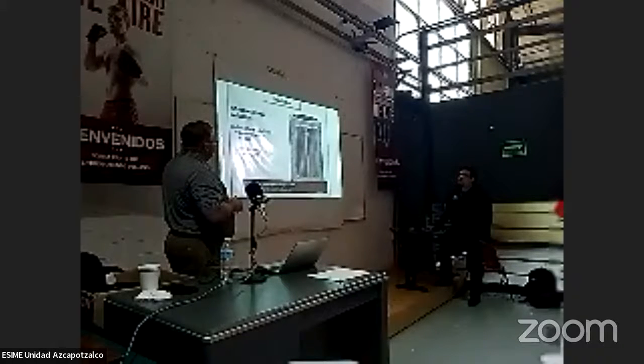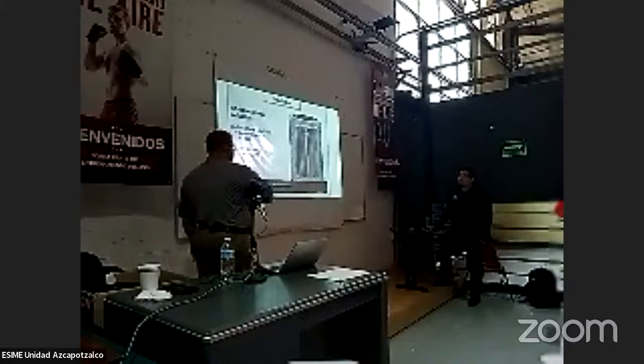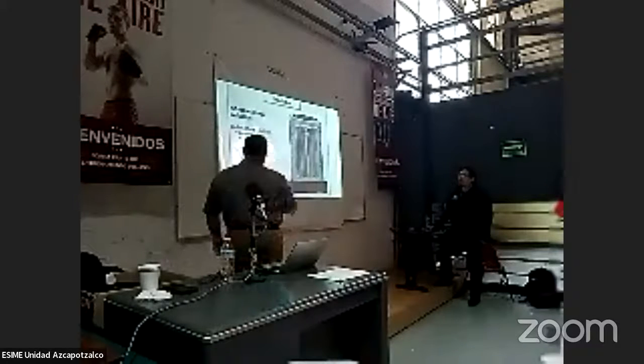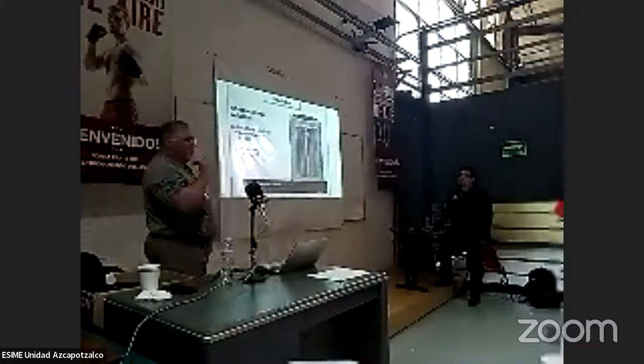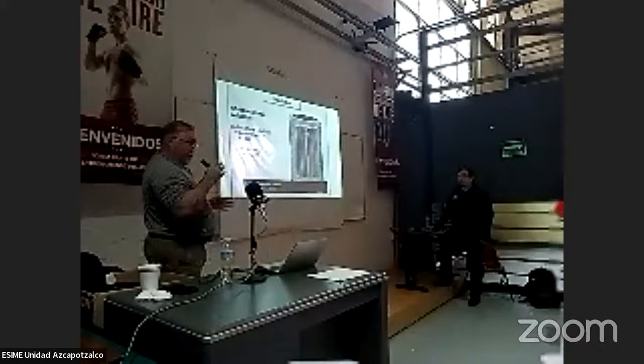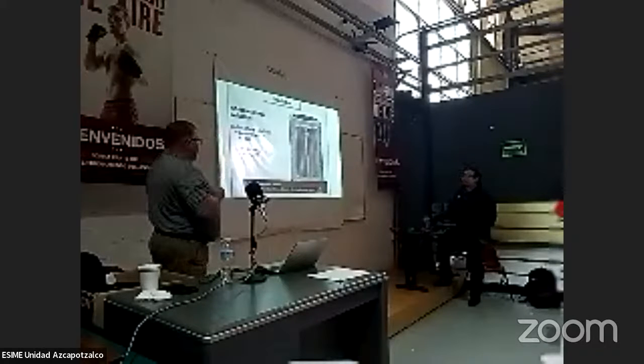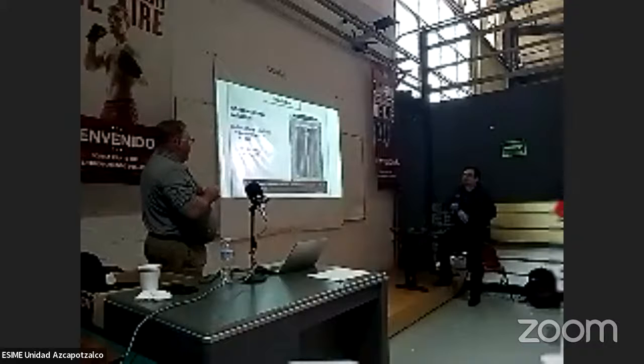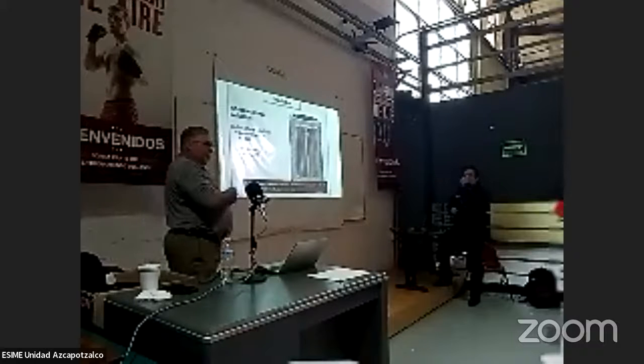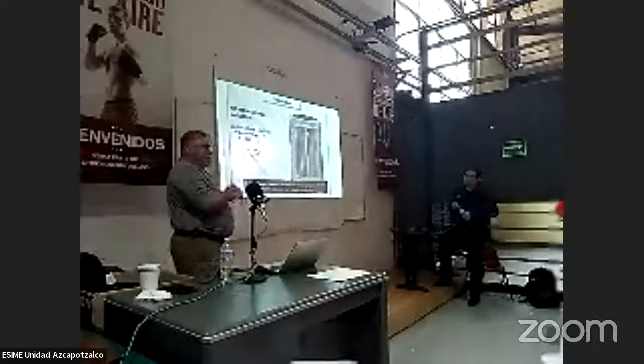When you're charging the system, you want the outdoor drive volt to be at least greater than 55, or 55 or better, right? Indoor drive volt should be more than 70, but less than 80, okay? Should be between 70 and 80.